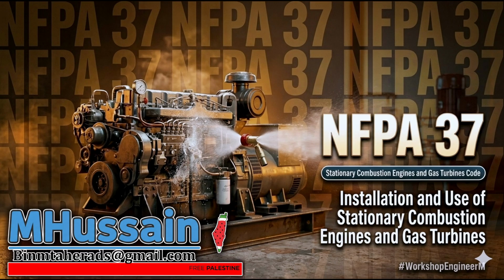So how do engineers actually prove it to the authority having jurisdiction, the AHJ? Do they, like, light a prototype on fire in a parking lot? I mean, essentially, yes. They rely on third-party laboratory fire tests provided by the manufacturer. But if I'm a fire marshal, I'd hate that. A lab test doesn't account for a blizzard with 40-mile-per-hour winds. Fire marshals do hate it. Think about the variables. Does the test assume the engine's massive cooling fan is running? Oh, right. Because a massive fan might actually blow the fire out.